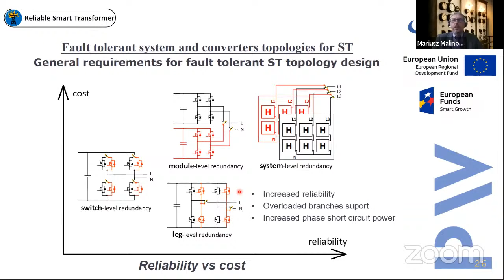We have module level redundancy, when extra modules are added, but it's costly. I think that this solution is more expensive. And we have the absolutely most expensive solution, which is system level redundancy. But analyzing everything, reliability versus cost, or post-fault operation ability versus cost, this one seems to be more attractive because it provides increased reliability. It supports overloaded branches and increases phase short circuit power. And how can it be done.